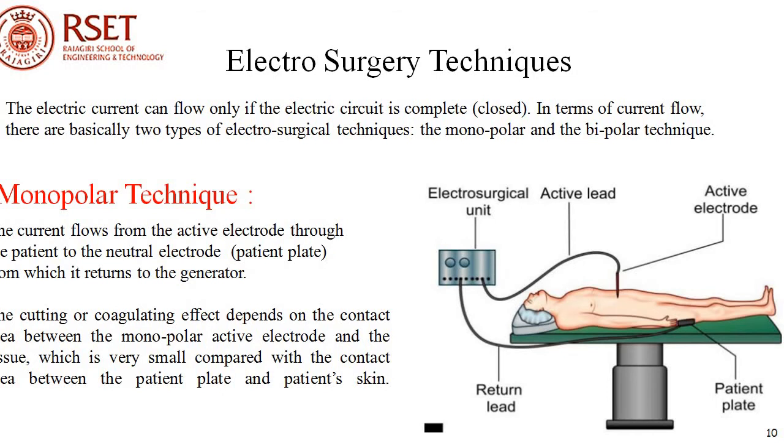The cutting and coagulating effect depends on the contact area between the monopolar active electrode and the tissue, which is very small compared with the contact area between the patient plate and the patient's skin.